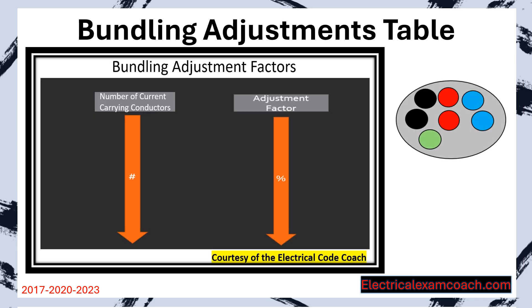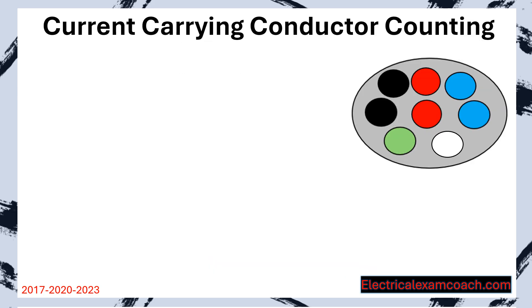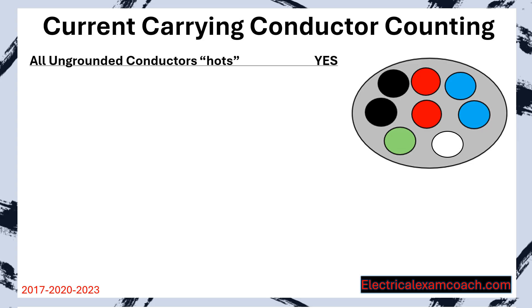Up until this point we've had all hot conductors inside our conduit. But what happens if we add in a neutral — is it considered a current carrying conductor? What about grounding conductors? Let's learn how to count conductors. We're only going to be counting the current carrying conductors. All ungrounded conductors — all of the hots — are going to be considered current carrying conductors under normal circumstances.